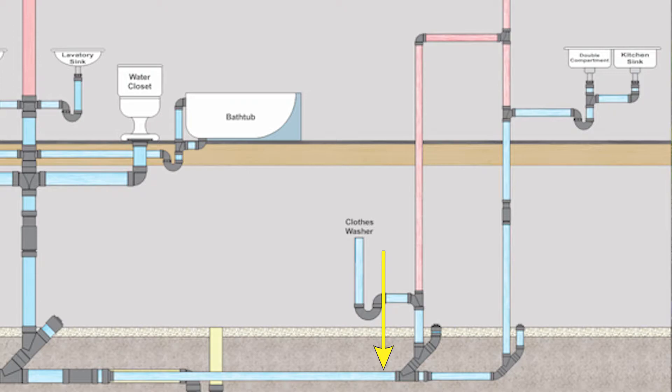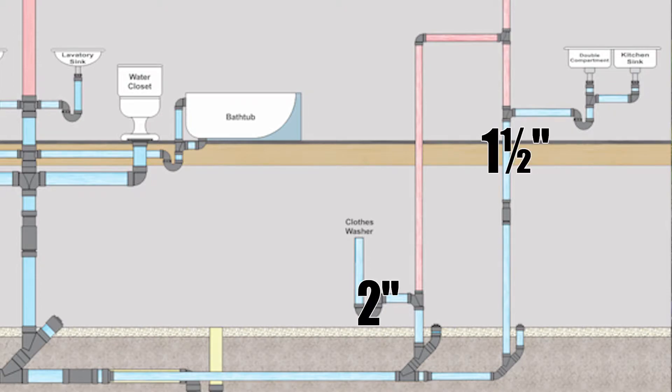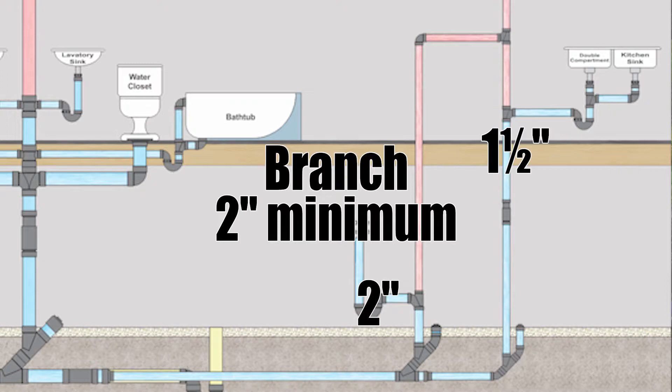Now this pipe right here is the result of two or more soil waste pipes joining together. Therefore we call it a branch. Now technically we need to use tables to size a branch but I said we're gonna keep it simple. I've got a two inch clothes washer and a one and a half inch kitchen sink. We are gonna have a two inch branch here.